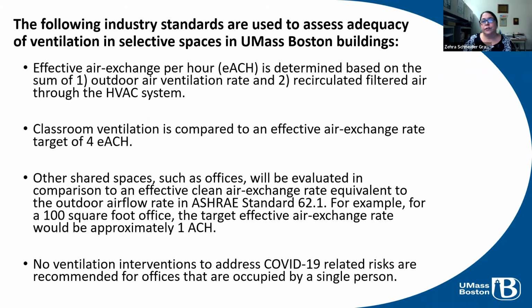So the following industry standards are used to assess adequacy of ventilation in selected spaces at UMass Boston. Effective air changes per hour, EACH, is determined by looking at the sum of the outdoor air ventilation rate and the recirculated filtered air through the HVAC system. For classrooms, that EACH rate is 4 air changes per hour.